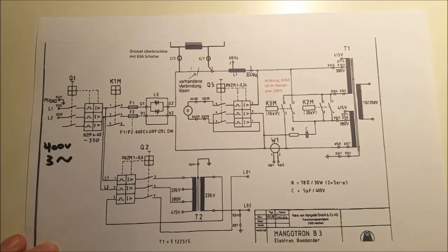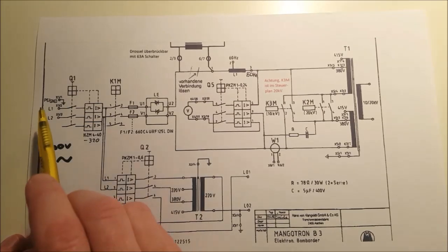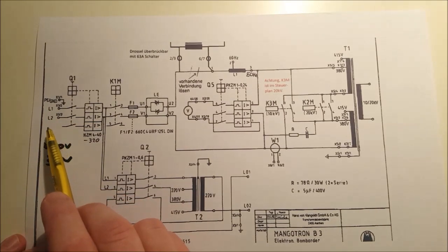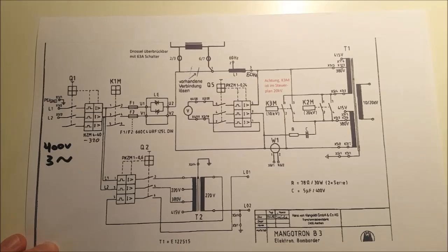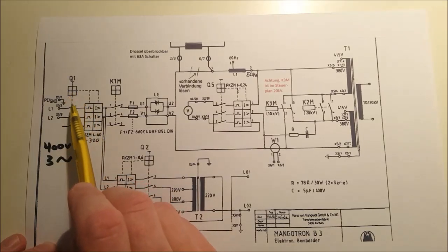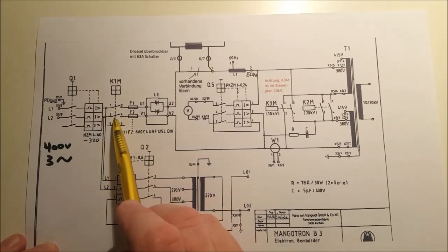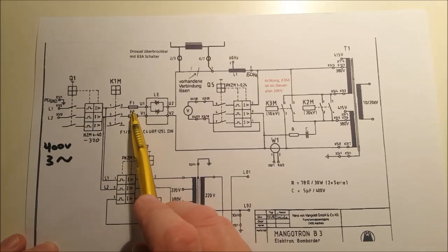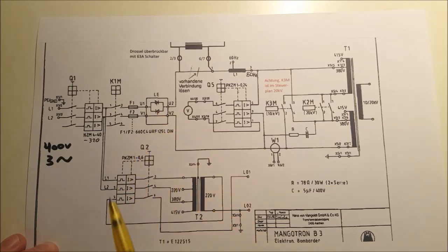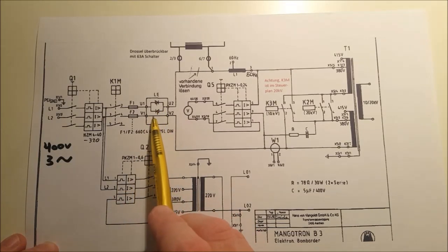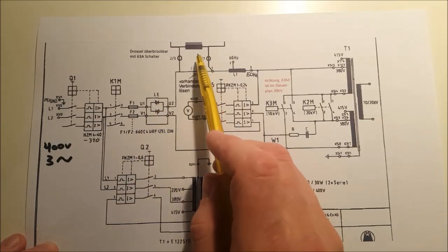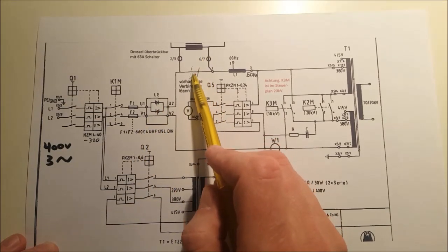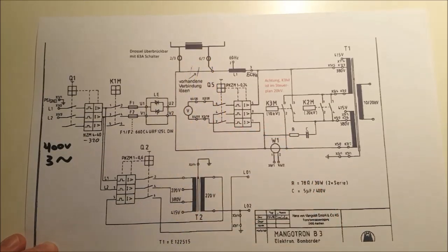This is the power wiring schematic. We have the line voltage coming in here. You see that only 2 phases of the 3-phase supply are used. Going through the main switch and main breaker, then the main contactor, the special fuses protecting the thyristor controller. Also interesting to see that one phase just passes through here and just one is controlled by the thyristors. Then up here we have a series choke, so this connection is interrupted. Series choke limiting the inrush current from the grid and limiting current spikes going through the tubing.